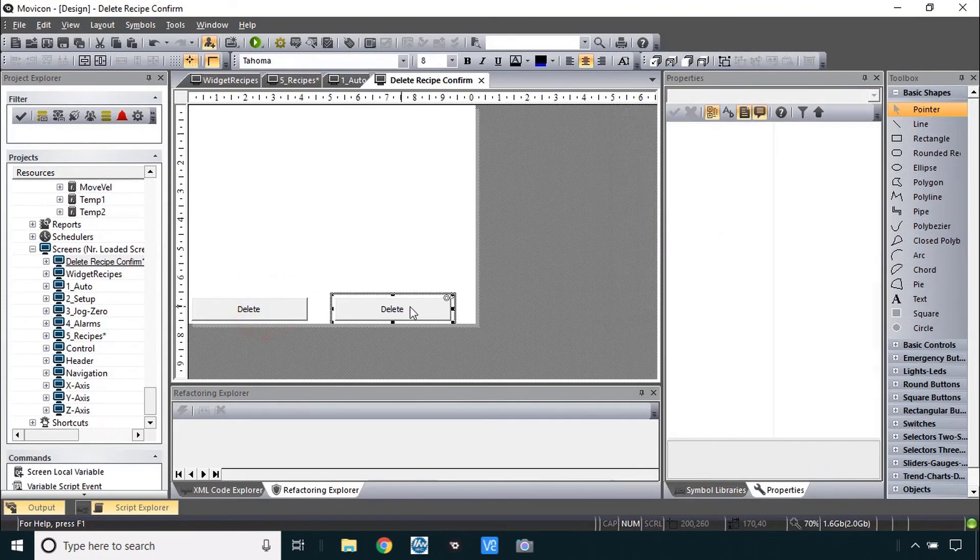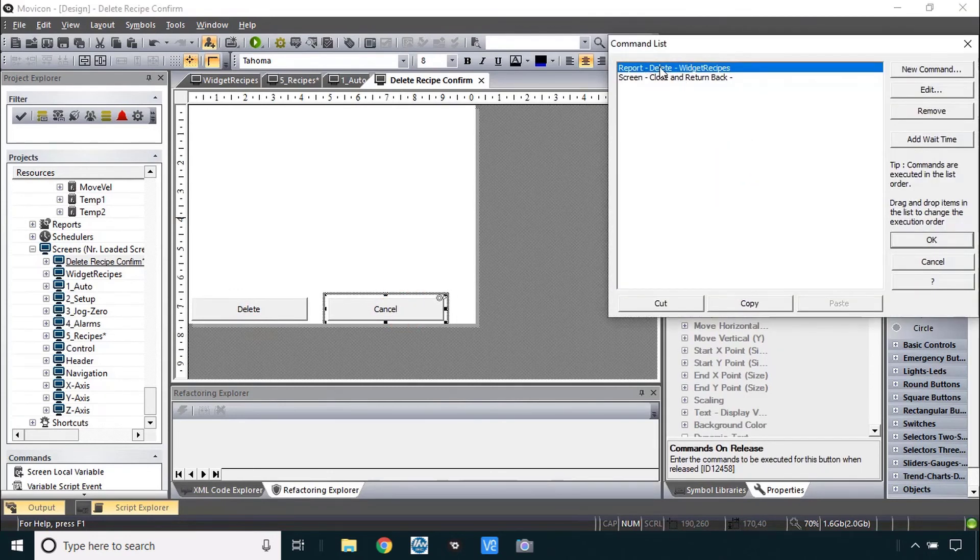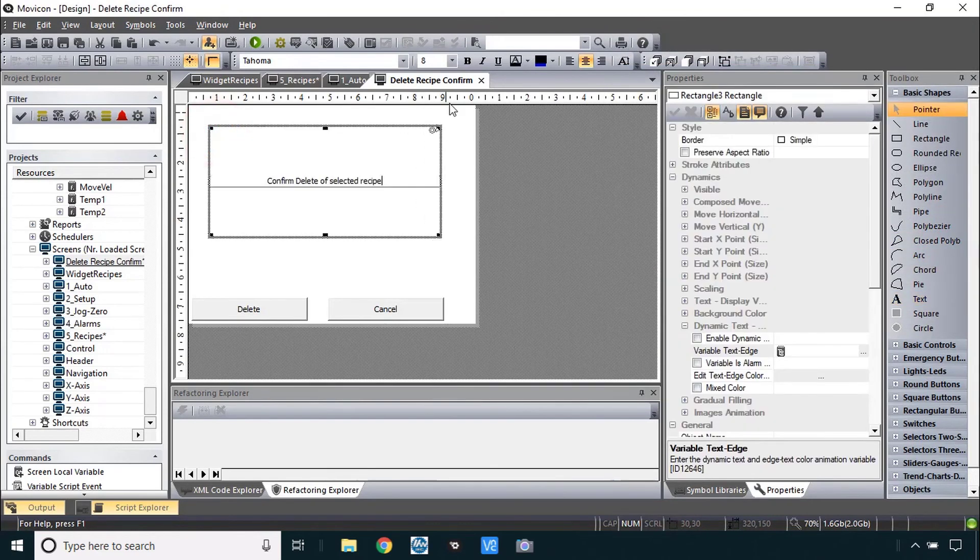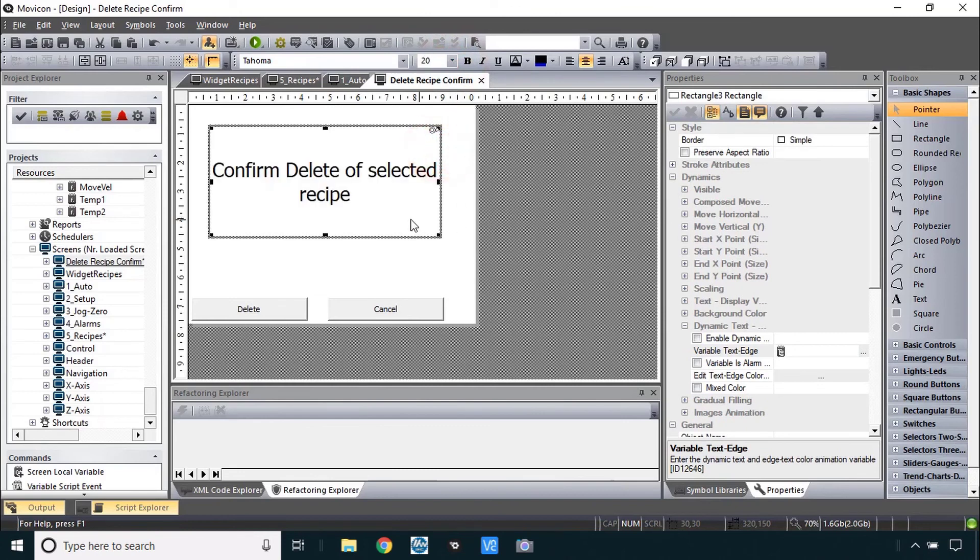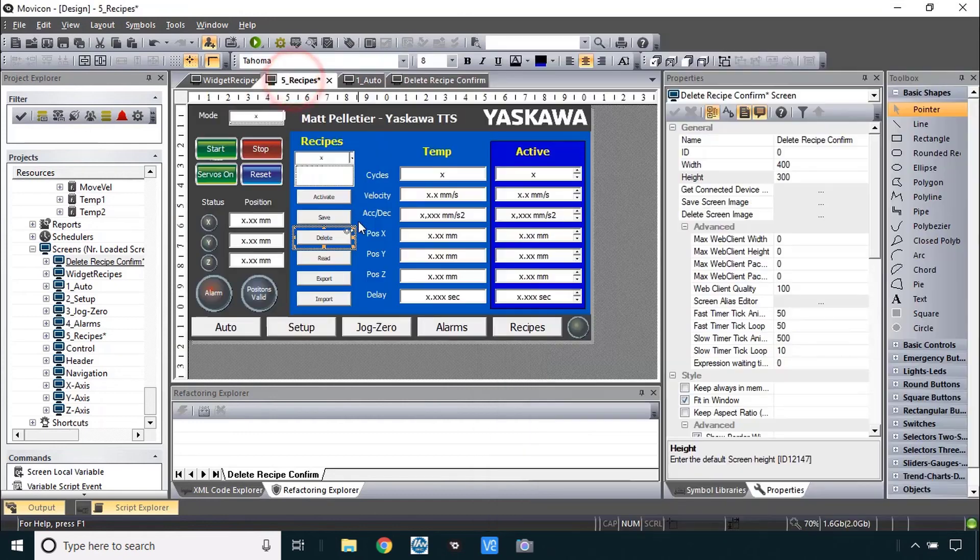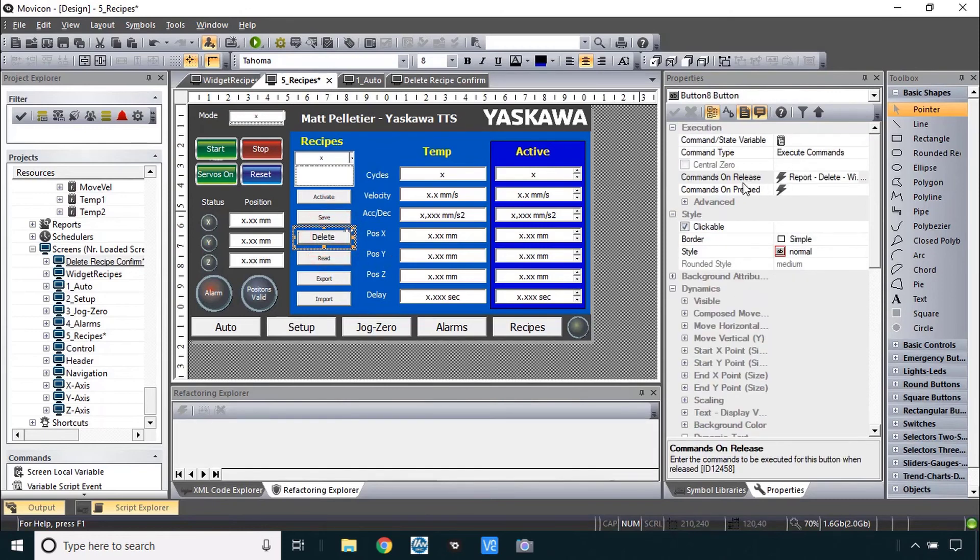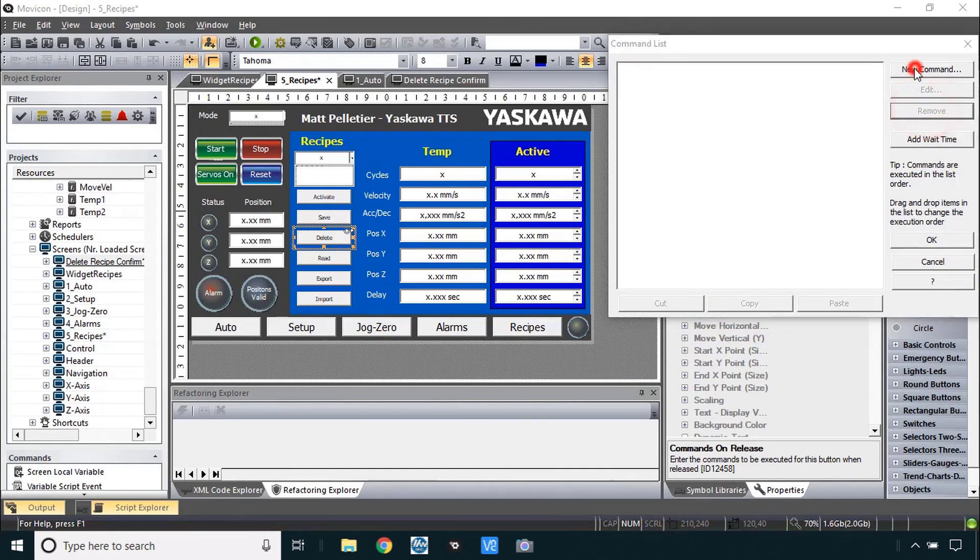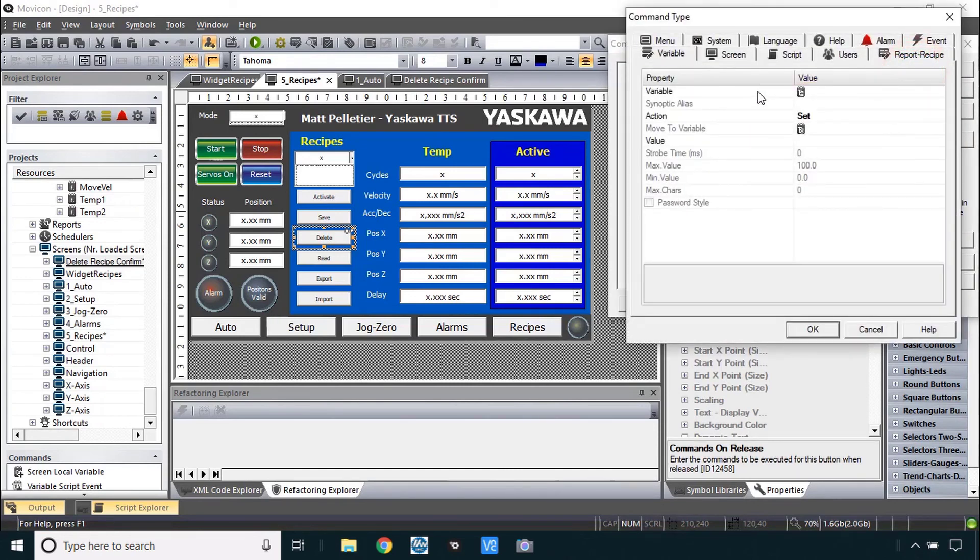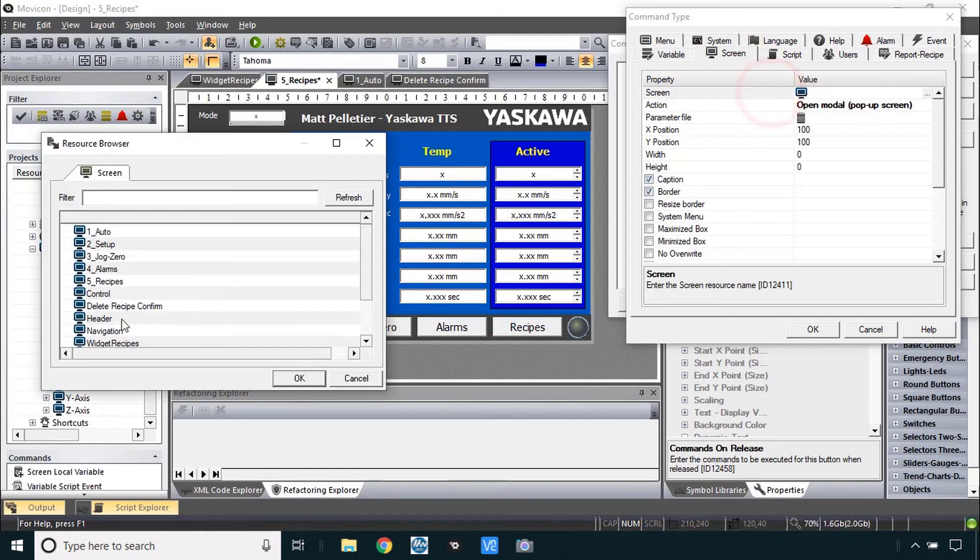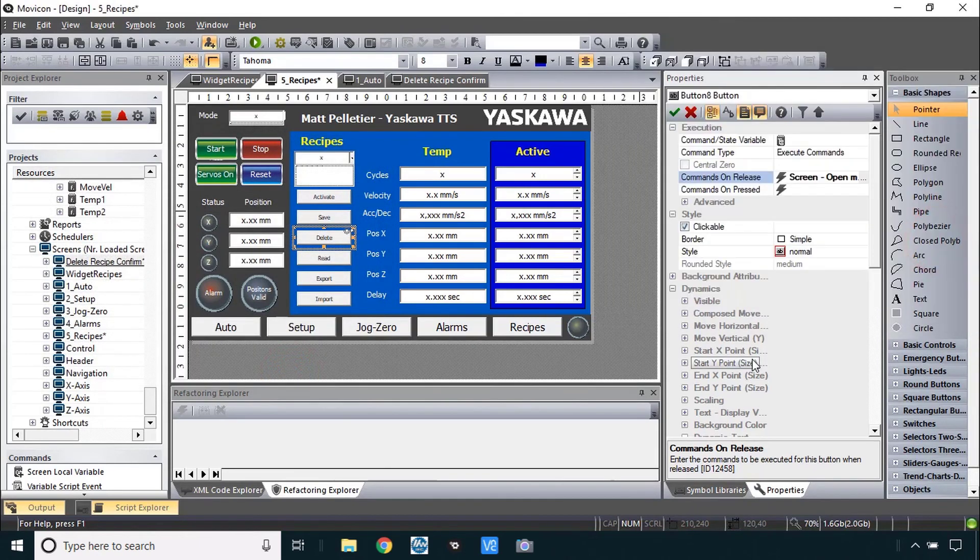I'm going to copy this button and paste it for the cancel button. I'll just call it cancel. And then in those commands I obviously don't want the delete part of it. So let's remove and just leave only close and return back. I should have a text on here. I'll call it confirm delete of selected recipe. Maybe make that a little bit bigger. And now it says change the command of the delete button from the recipe screen to open modal pop-up screen. Right. So back to recipes. We don't want this delete button to actually delete. I'll be sure I click on it. The command that it executes should be simply to here not delete. I'll remove that and make a new command. It's a screen command to open as a pop-up screen. And that screen will be the screen we just created. Delete recipe confirm.